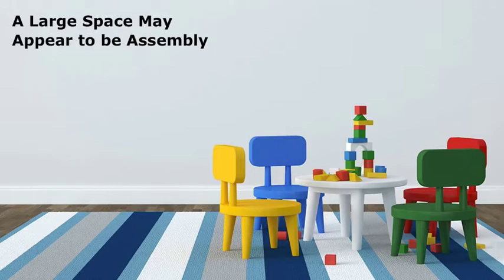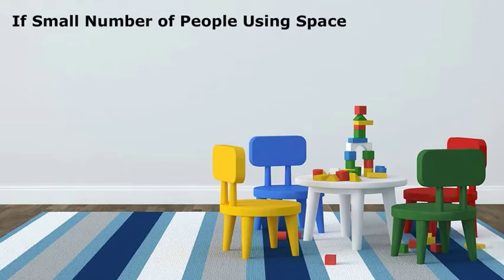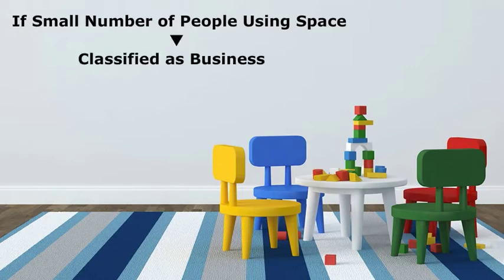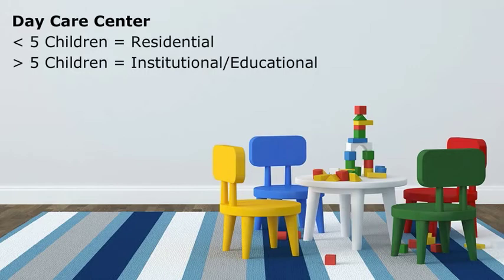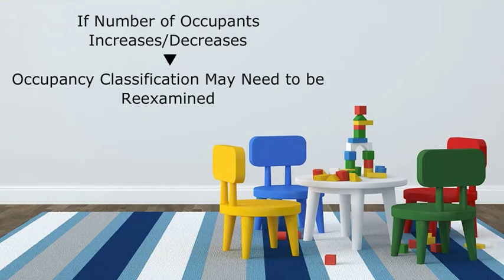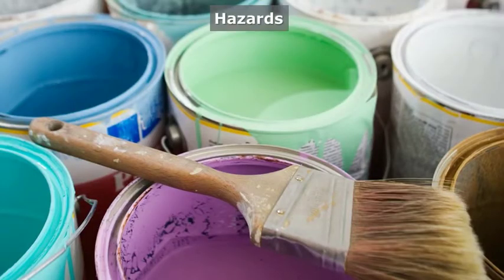Many of the classifications allow for a specific number of people. For example, a space may appear to be an assembly use, but if a small number of people will be using the space it may be allowed to be classified as business when using the IBC. If a daycare center has fewer than five children, it may be considered residential, but if it has more than five it may be considered institutional or educational. So if the number of occupants increases or decreases, the occupancy classification may need to be reexamined.